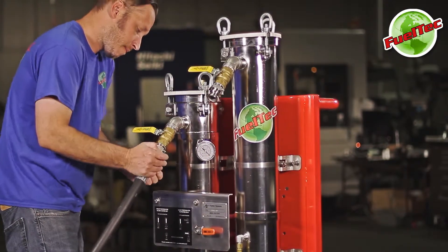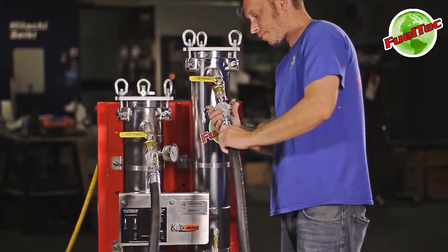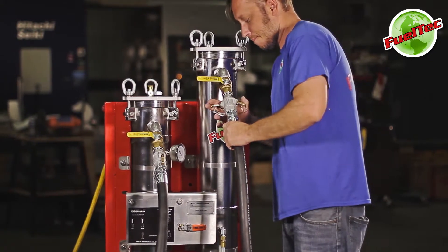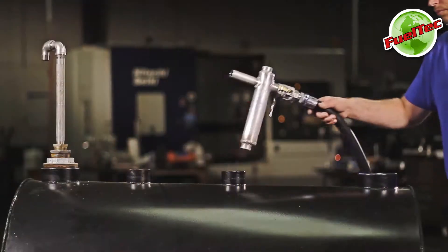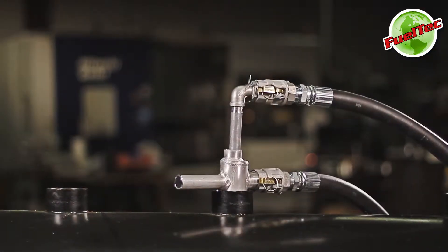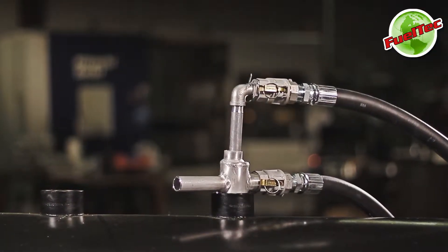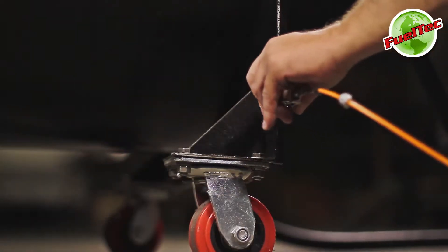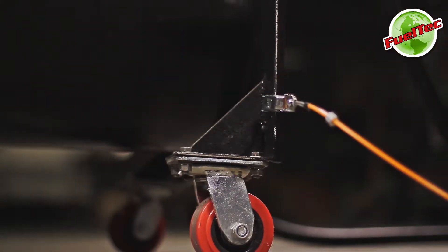Connect the suction hose to the primary filter inlet. Connect the return to tank hose to the water separator outlet. Insert the return to tank manifold into the tank opening. Insert the fluid pickup tube through the manifold into the tank. Connect the static ground cable to the tank to prevent sparks.